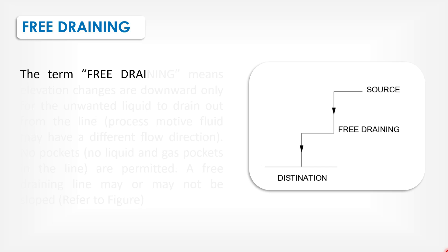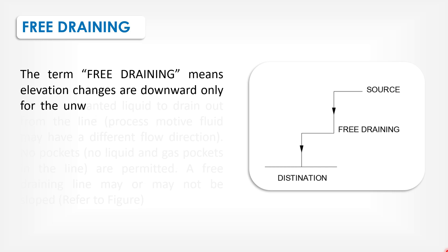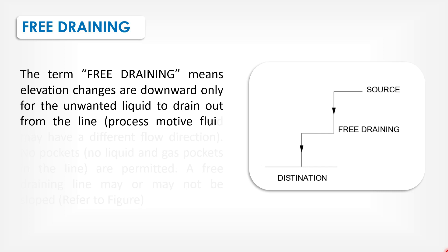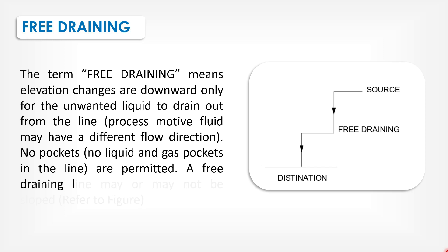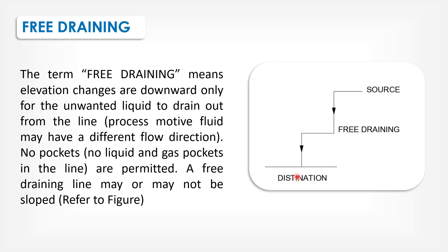The term free draining means elevation changes are downward only for the unwanted liquid to drain out from the line. Process motive fluid may have different flow direction. No pockets - no liquid and gas pockets in the line are permitted. A free draining line may or may not be sloped. Therefore, the figure slopes to destination.